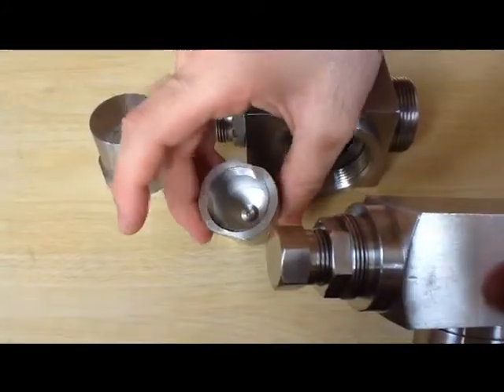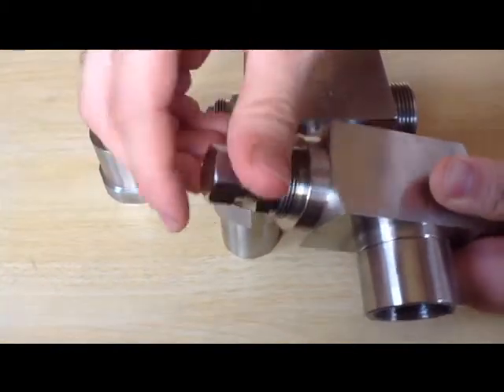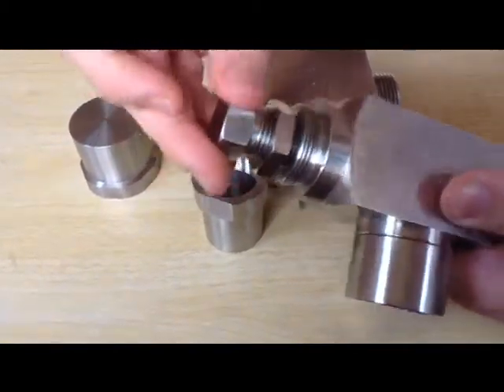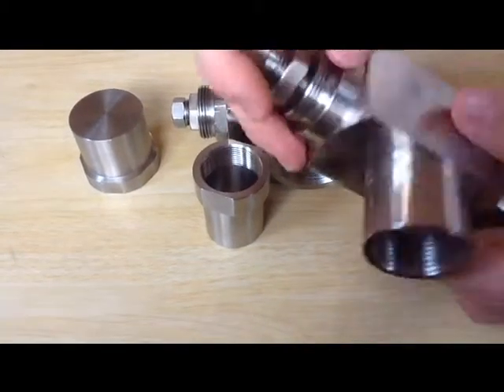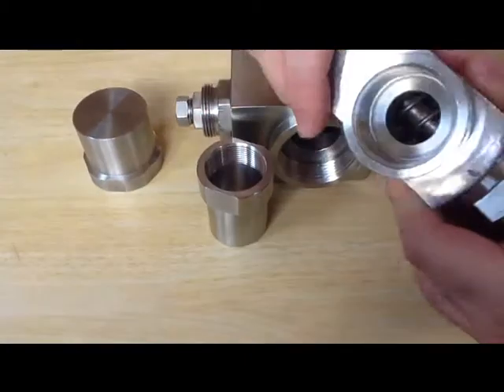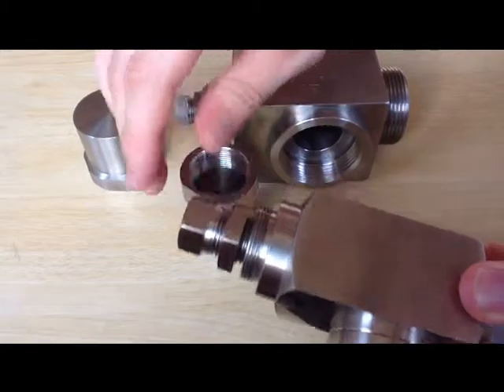A pressure relief valve is a safety device designed to protect a pressurized vessel or a system during an over-pressure event. An over-pressure event refers to any condition which could cause pressure in a vessel or a system to increase beyond the specified design pressure or maximum allowable working pressure.